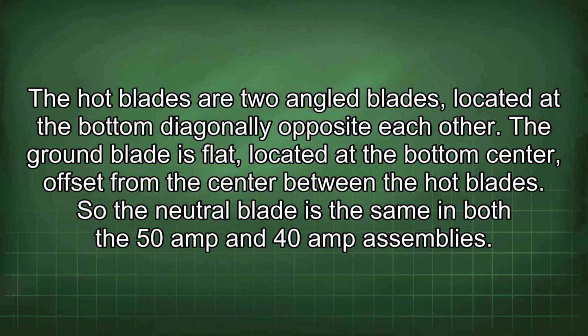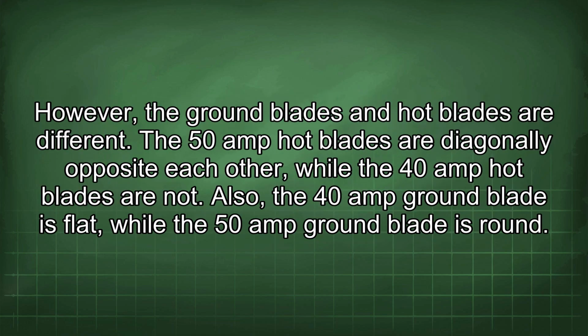So the neutral blade is the same in both the 50 amp and 40 amp assemblies. However, the ground blades and hot blades are different. The 50 amp hot blades are diagonally opposite each other, while the 40 amp hot blades are not. Also, the 40 amp ground blade is flat, while the 50 amp ground blade is round.